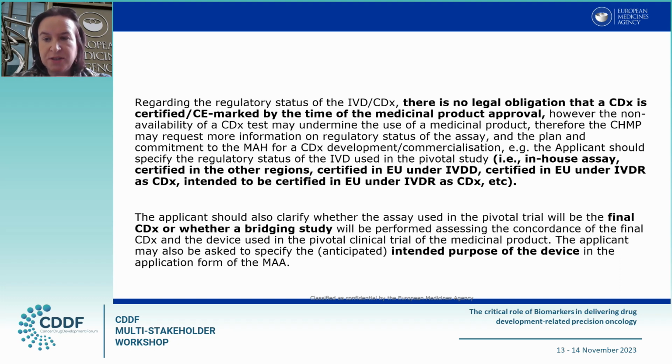This new legislation introduces the definition of a companion diagnostic. A companion diagnostic is a device which is essential for the safe and effective use of the corresponding medicinal product to identify patients who are most likely to benefit from that medicinal product. On this, there is no legal obligation that the companion diagnostic is certified, CE marked, by the time of the medicinal product approval.